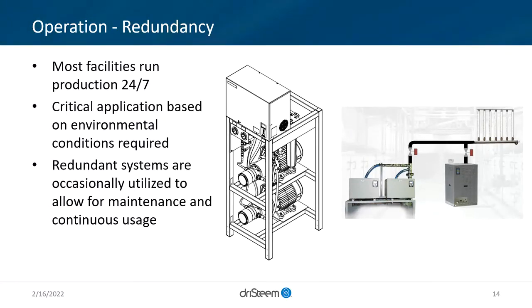The first depiction on the screen is a high pressure atomization pump station, where within that it's essentially an N+1 depiction for the pump itself. On the right side, we have examples of electric resistive units along with gas to steam. That's a way you can do redundancy regarding multi-tank control for the vapor mist in this case, and then the larger load of GTS.